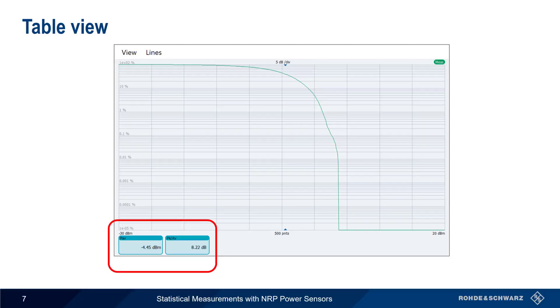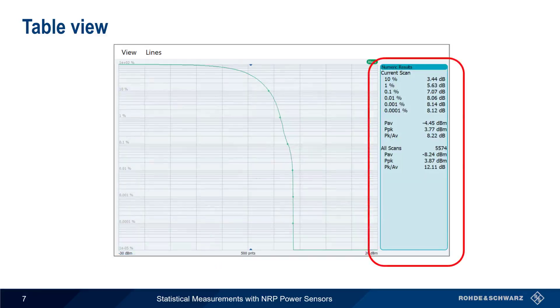When making CCDF measurements, PowerViewer also provides a table view. Simply right-click in the graph and choose Table View to display the tabular results. The percentage values show how often the signal reaches or exceeds a given level. In this example, our signal is at or above 5.63 dB 1% of the time, and is above 8.14 dB only .001% of the time.